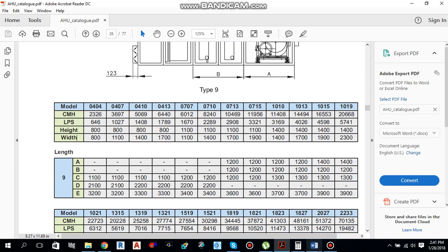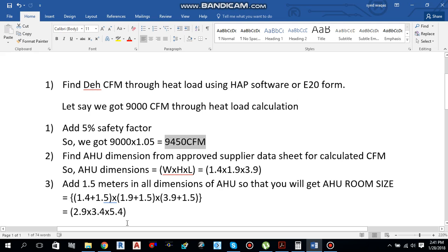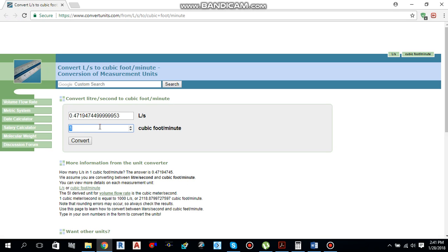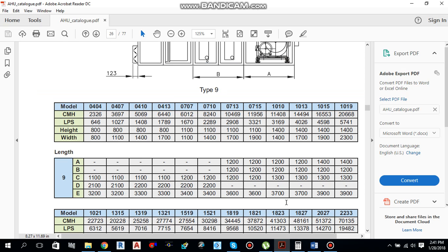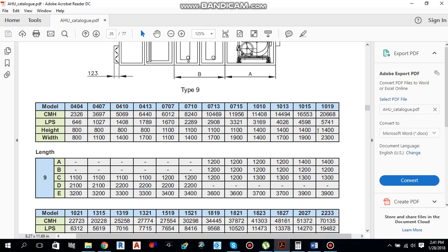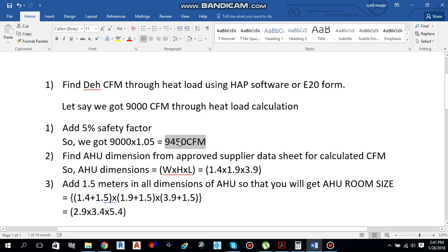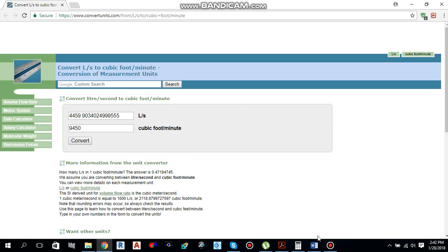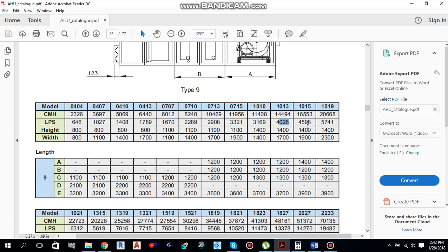We have 9450 CFM. Converting this to liters per second gives us 4459, which is around 4460 liters per second. Moving back to the catalogue, the closest value on the higher side is 4598 liters per second. We always go for the higher side, not the lower side, so we select the unit rated at 4598 liters per second.